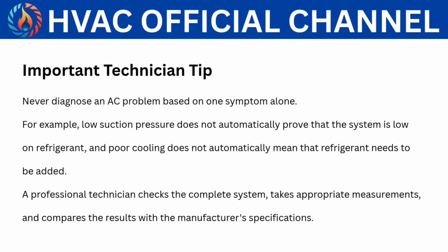Important technician tip: never diagnose an AC problem based on one symptom alone. For example, low suction pressure does not automatically prove that the system is low on refrigerant, and poor cooling does not automatically mean that refrigerant needs to be added. A professional technician checks the complete system, takes appropriate measurements, and compares the results with the manufacturer's specifications.